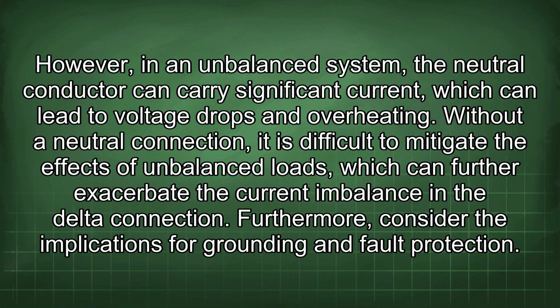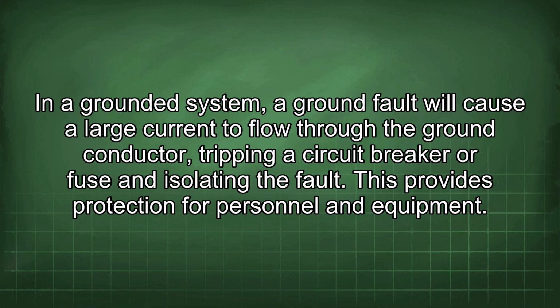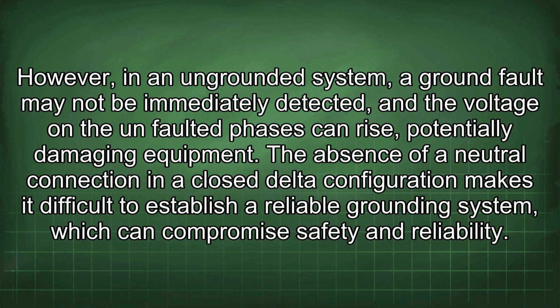Furthermore, consider the implications for grounding and fault protection. In a grounded system, a ground fault will cause a large current to flow through the ground conductor, tripping a circuit breaker or fuse and isolating the fault. This provides protection for personnel and equipment. However, in an ungrounded system, a ground fault may not be immediately detected, and the voltage on the unfaulted phases can rise, potentially damaging equipment. The absence of a neutral connection in a closed delta configuration makes it difficult to establish a reliable grounding system, which can compromise safety and reliability.